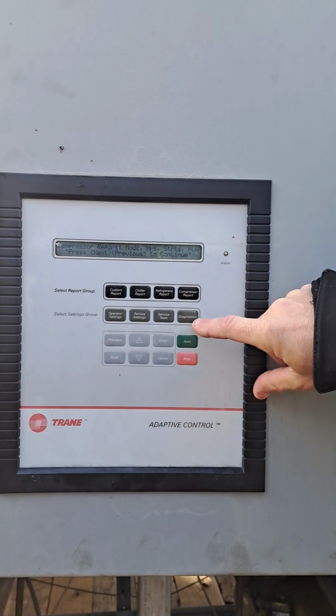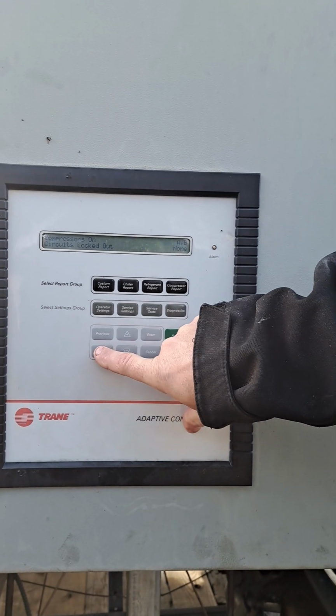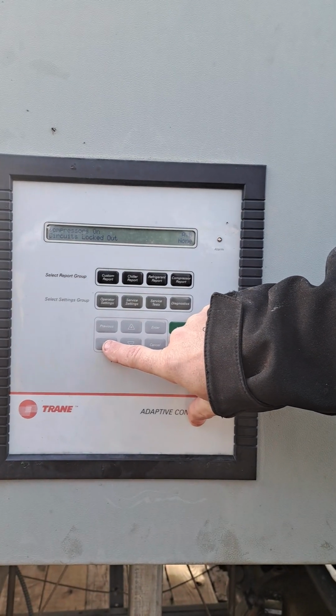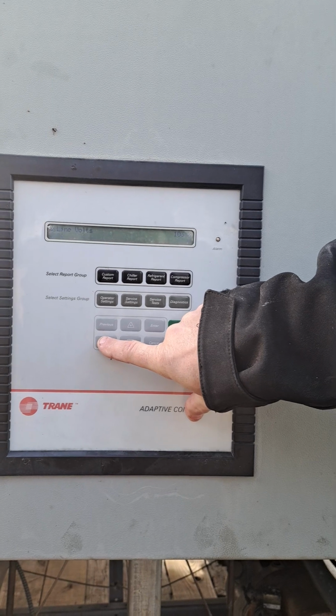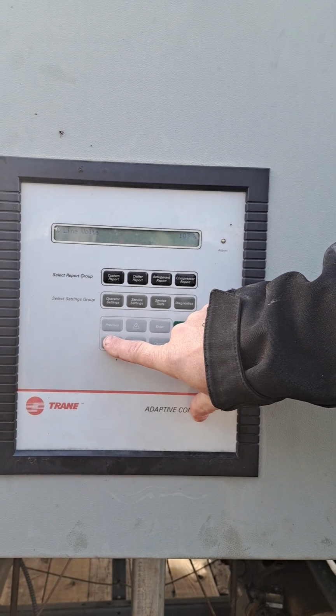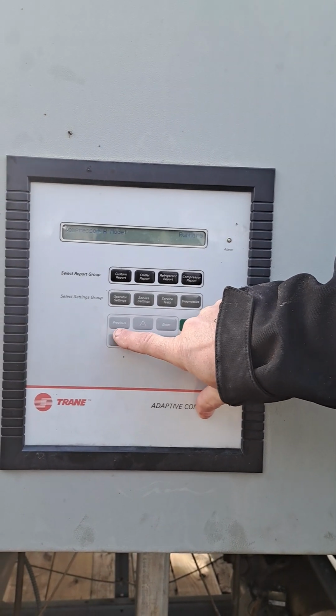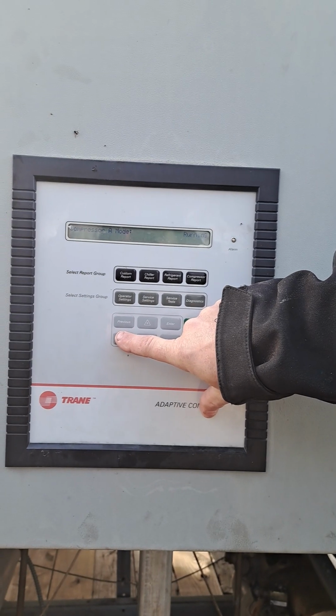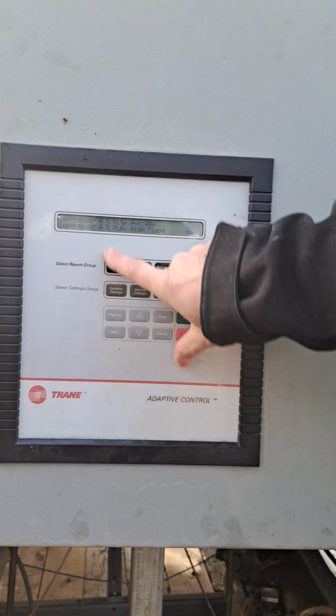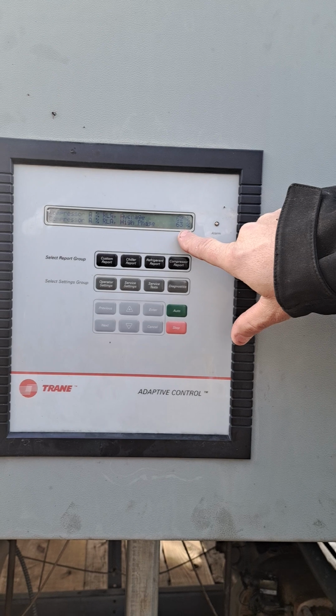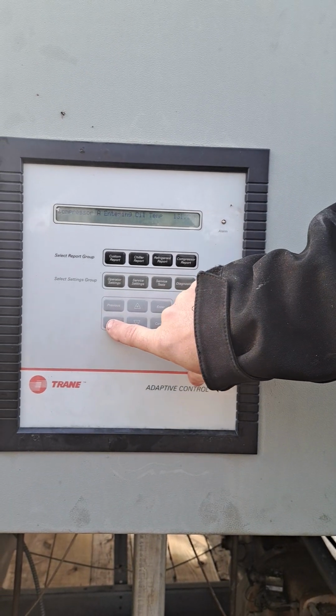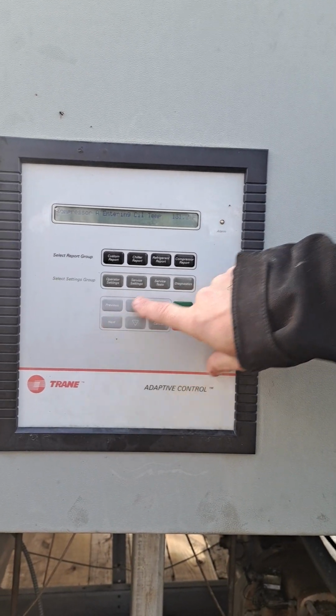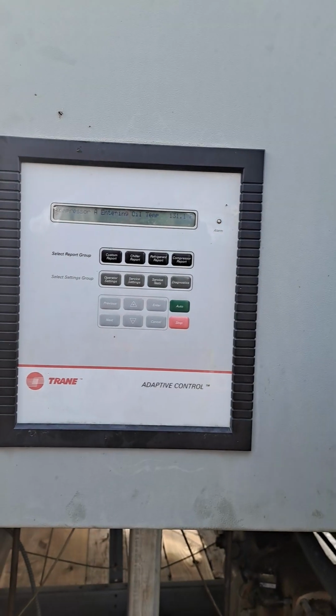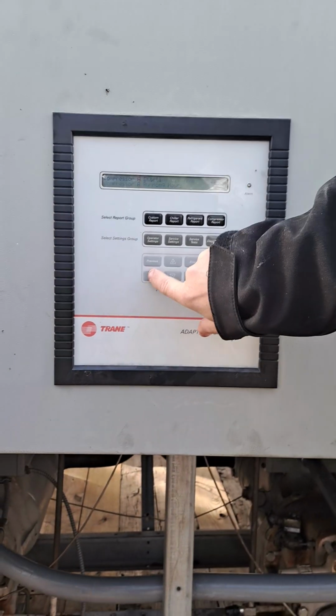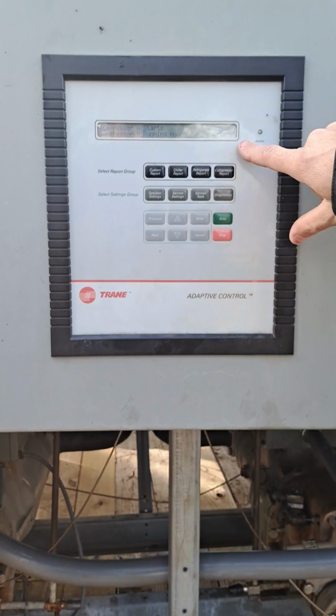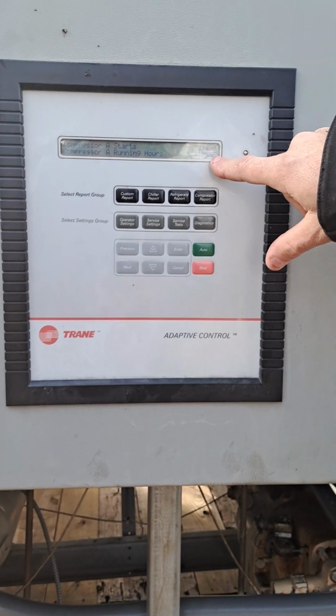You have the compressor report. So that tells you right now both compressors are running, nothing's locked out. That gives you your 103% of line voltage. Shows you which compressors are running, shows you the percentage that they're at. And then there's your oil temperature there. We're 130 degrees on that circuit. And then as you keep scrolling through, there's your starts and hours.